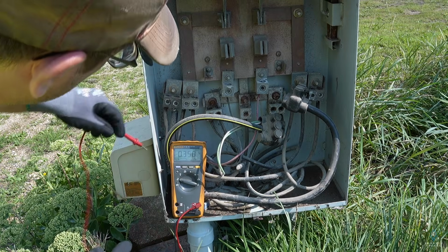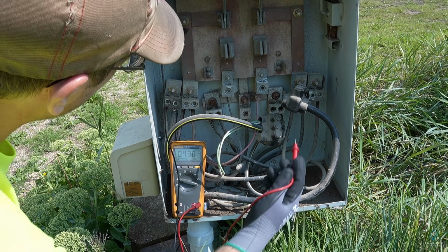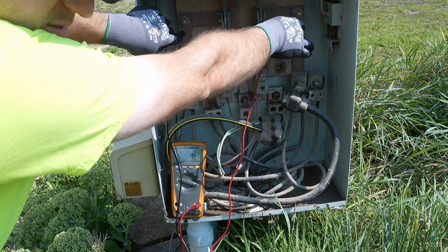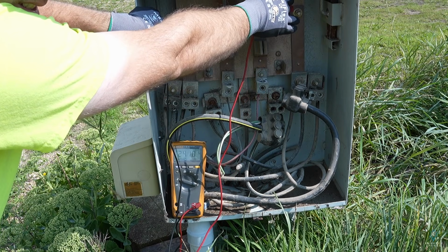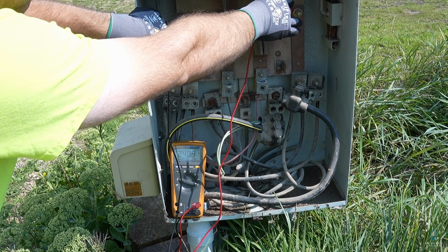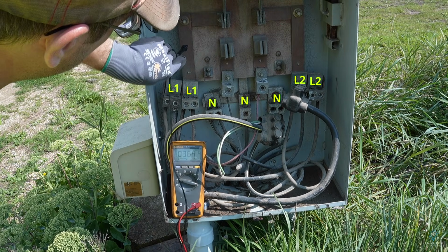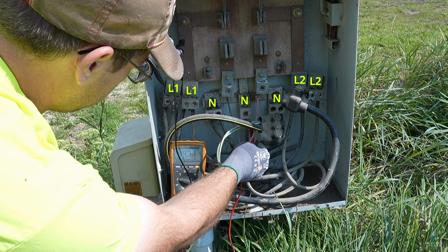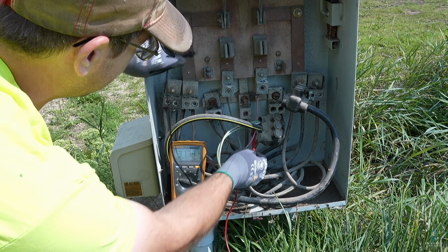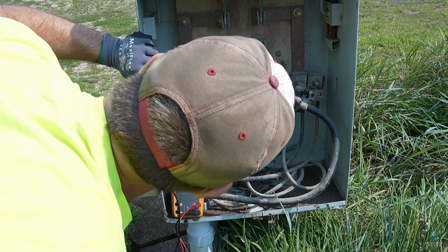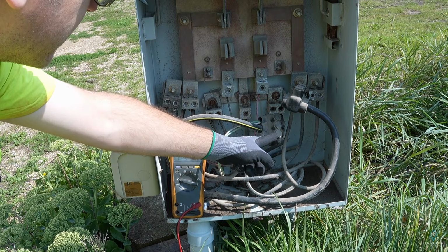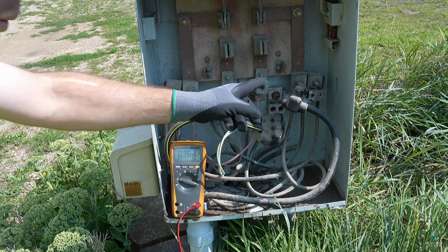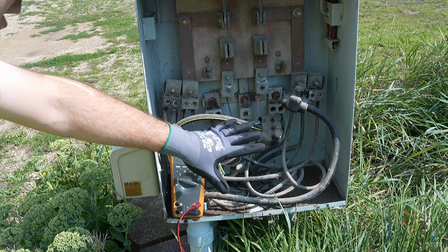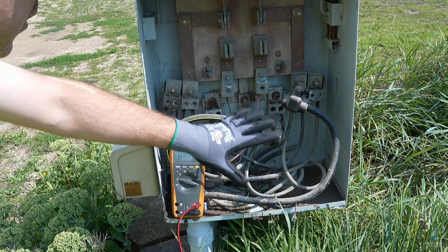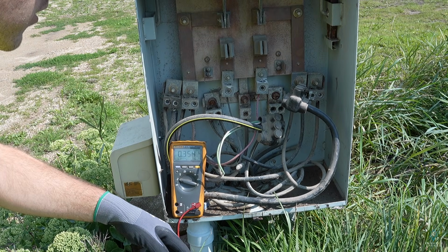Let's see if we can actually observe this voltage issue. From here to here, 240 volts. And we do indeed have that. So from here to neutral, it's reading 40 volts because that thing is so corroded. That's why they put the Polaris connectors here. I bet it was so corroded originally when they did this service change, 15, 20 years ago, that they didn't even want to mess with the original lugs.